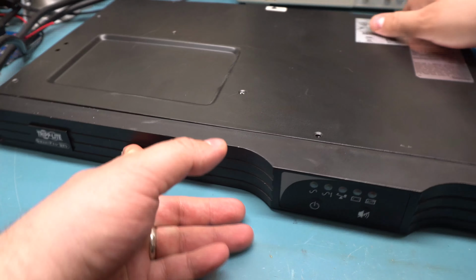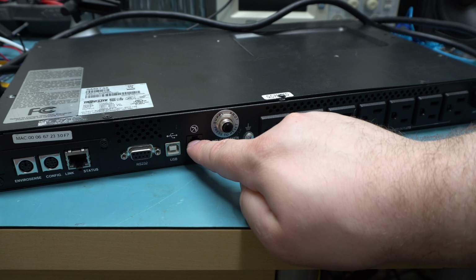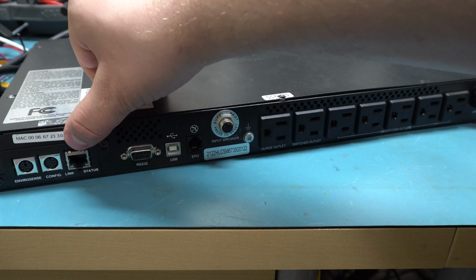There's a ground hookup. I don't know what the EPO is — that's probably their own proprietary serial connector. There's also an option card installed that has an Ethernet port, a configuration port which is probably serial, and an EnviroSense port, which I believe connects to different monitoring things like fire, that kind of stuff, and possibly temperature as well, which can trigger shutdowns if certain conditions are met, like an emergency.